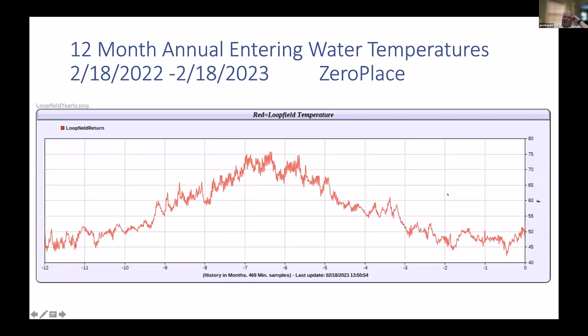So there was a lot of in and out of energy, which we didn't account for, or which we were unable to model for, which is actually what we're measuring and seeing. But the point is, we start to put energy in, we heat up the ground to about 75 degrees, then we're entering heating season and we're getting this energy back. And then the loop field simply does not budge anymore, no matter how cold it gets outside. Again, we measured -6 degrees outside temperature. This is where this is going down a little bit in the beginning of February. But other than that, it was a reliable source of energy and it was always delivering.